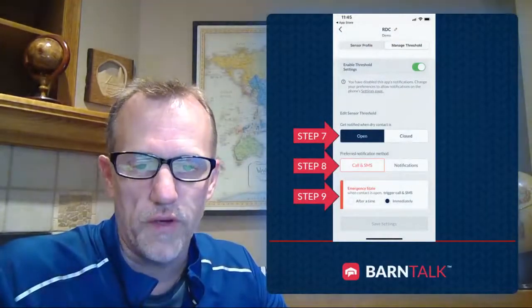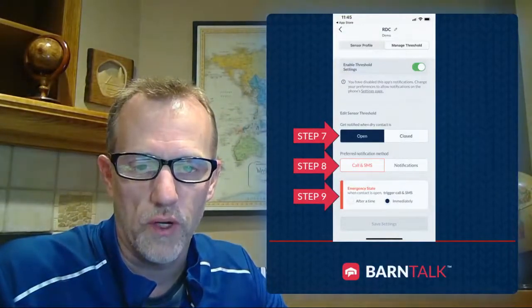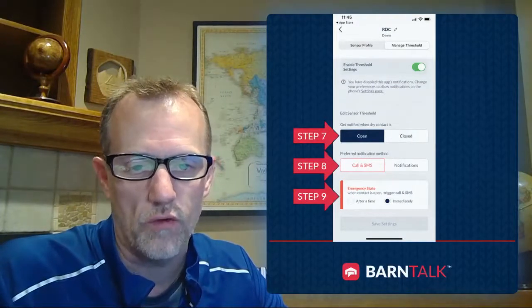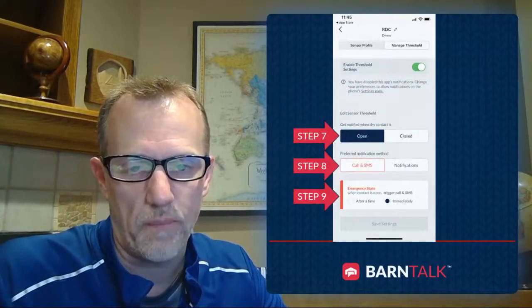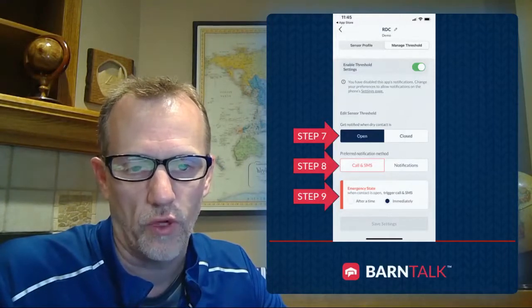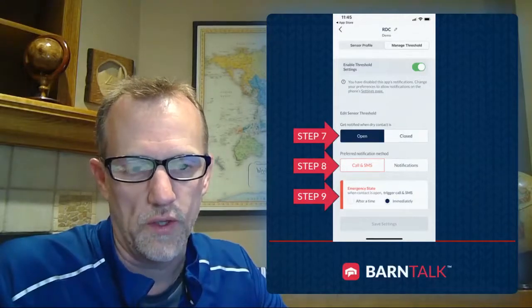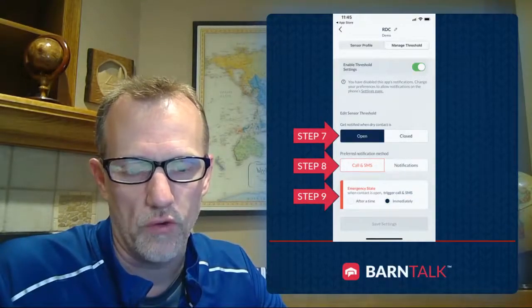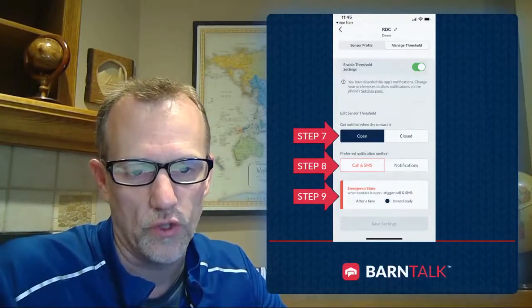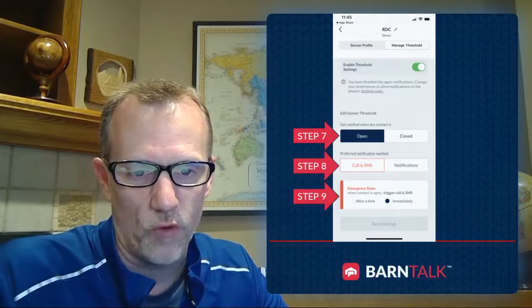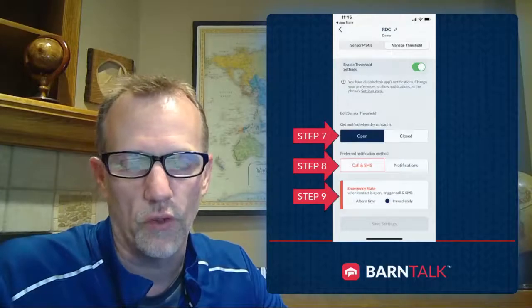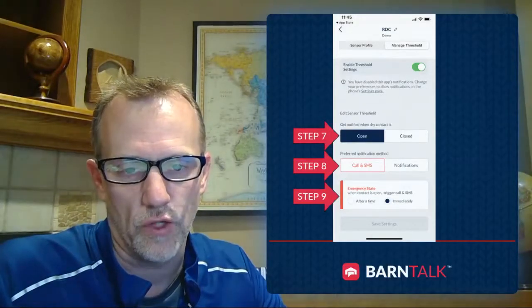We have three different settings available for the dry contact alerts. Step 7 is when you want to get notified. This tells the app to notify you when the dry contact state changes from closed to open. If you click on closed, you will be notified when the circuit wired into the dry contact goes closed. If you have a normally open circuit, you want to be notified when it closes; if you're using a normally closed circuit, you want to be notified when that circuit opens.